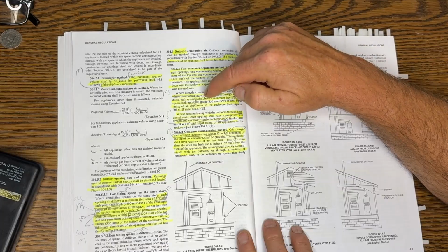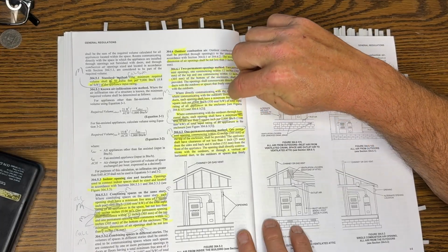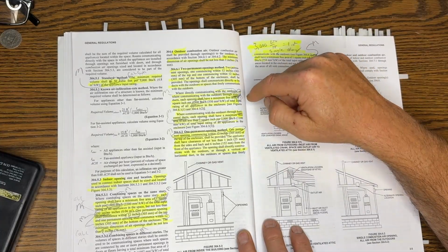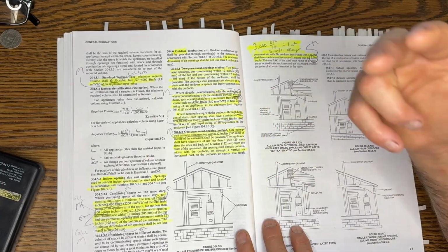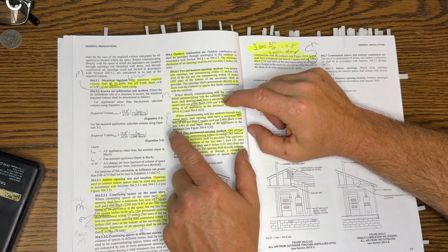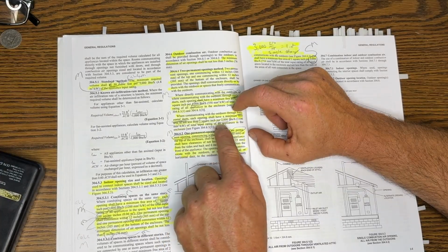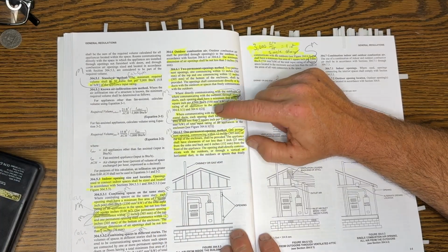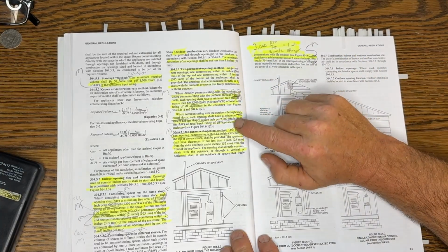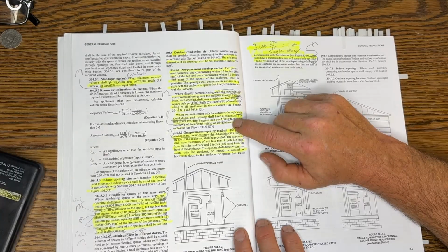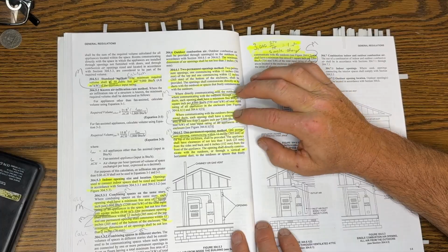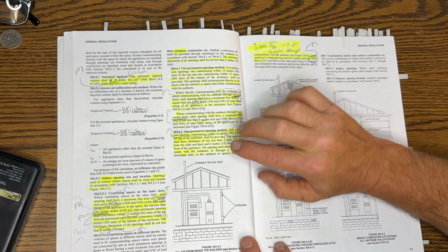I'm reading this, there it is: each opening shall have a minimum free area of 1 square inch per 4,000 BTU. So if they're asking for just one opening, it would be 1 per 4,000, but if they're asking what is the overall opening size, it's 2 square inches per 4,000. And when communicating with outdoors through horizontal ducts, each opening shall have a minimum free area of not less than 1 square inch per 2,000 BTU. So you have to have double the area if you're going through a duct communicating with the outdoors rather than something permanently through the wall. Okay, so just remember that.